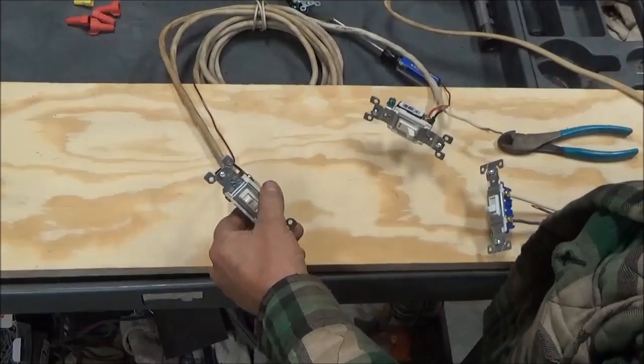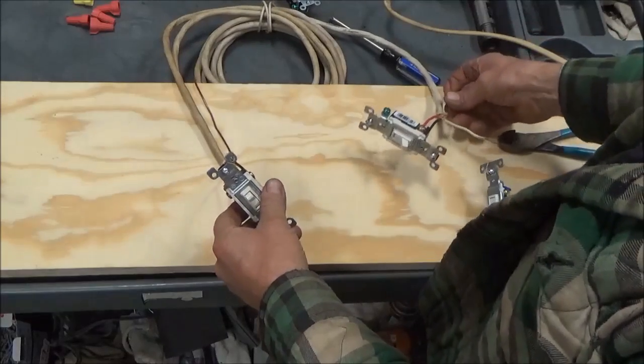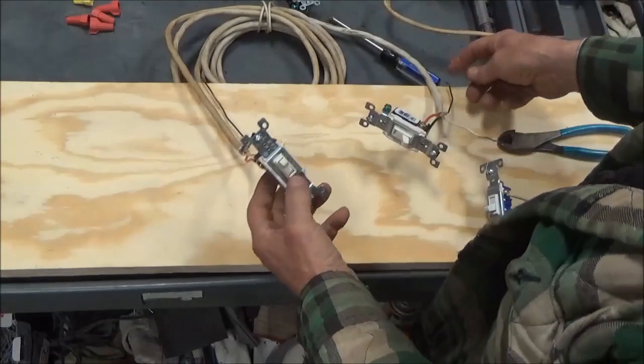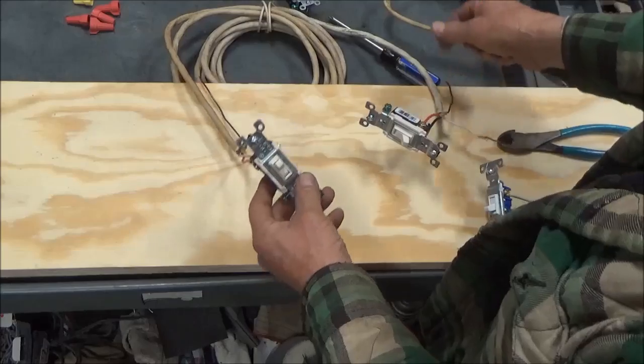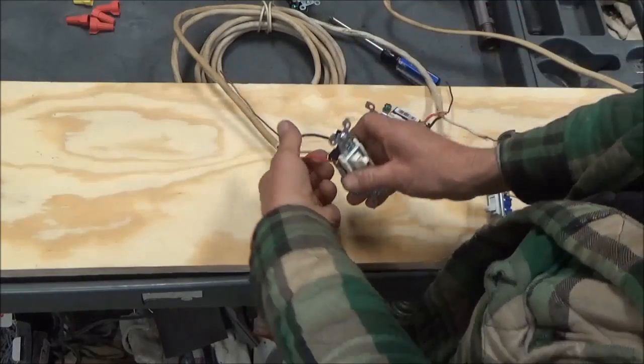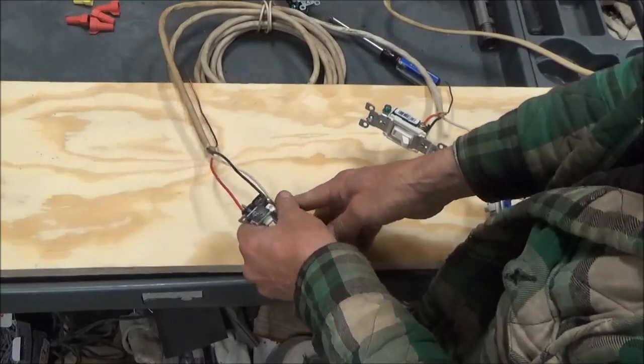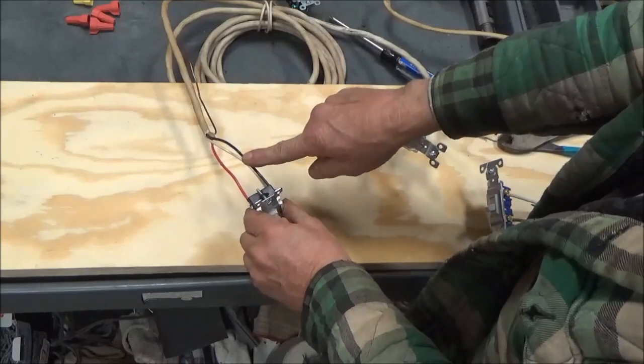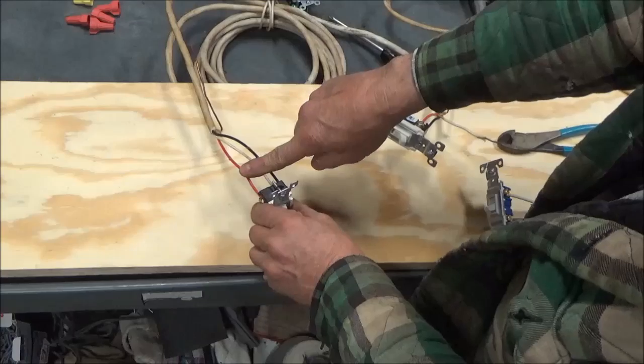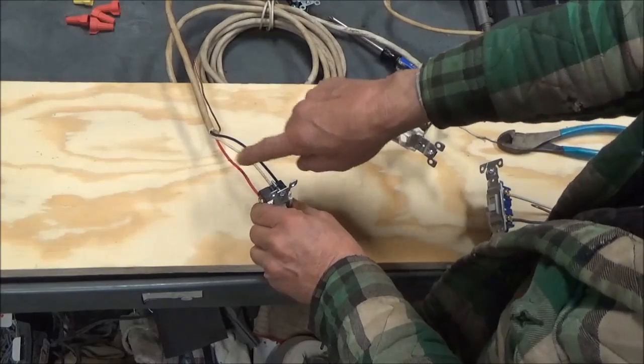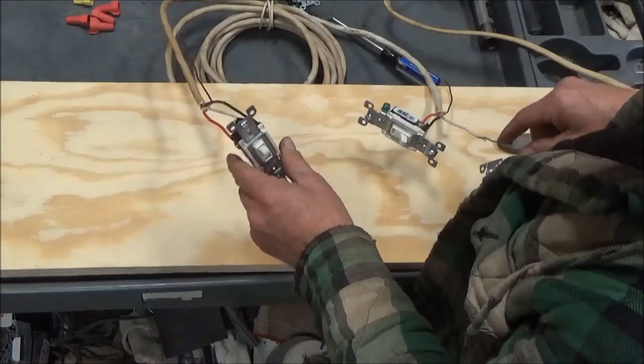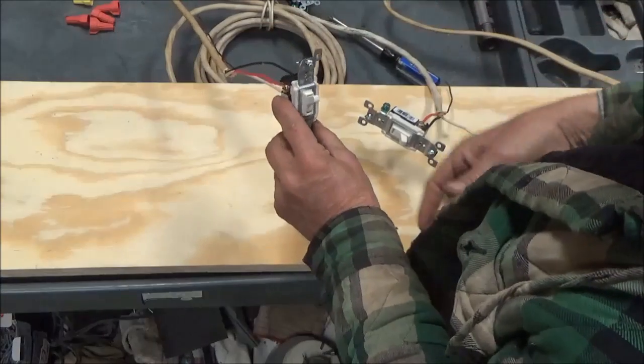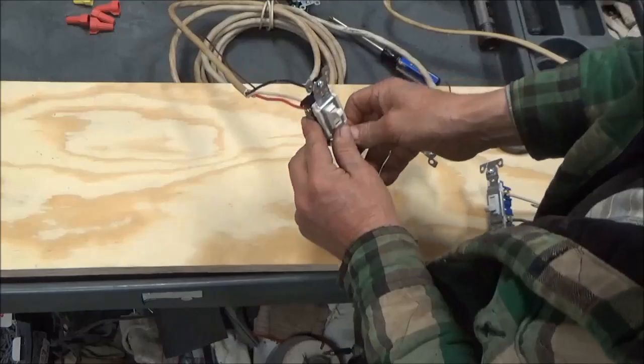What I've done now is I've hooked up a piece of 12-3 with ground wire. Once again, for demonstration purposes only, we're not using the ground. That's just an emergency escape in case something goes wrong with the circuit. We don't need it for this. And the reason I'm using 12-3 with ground is because it has, the neutral is still the white wire, and the black is still the hot, but there's another wire, the red one, is also a hot. And it doesn't matter which one you use, they're both hot, could be used in either place of each other. But they help you identify which one is which at the other end of a circuit.